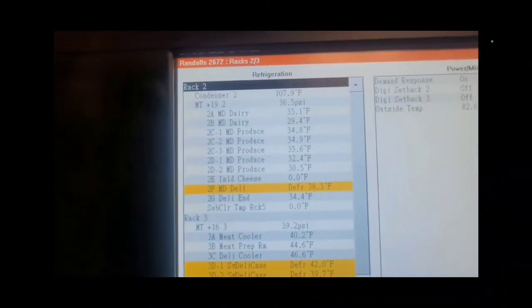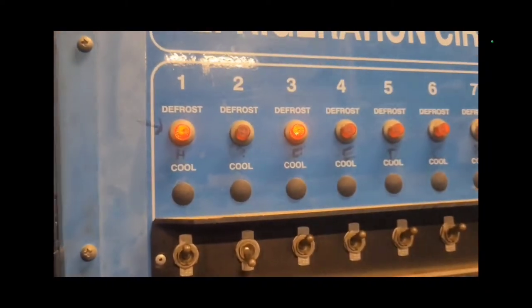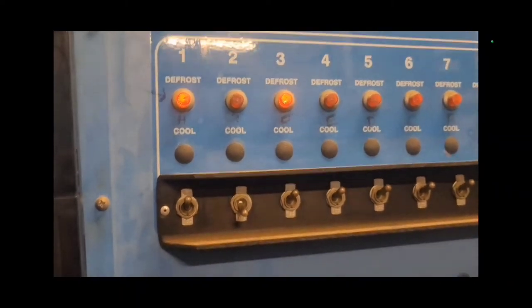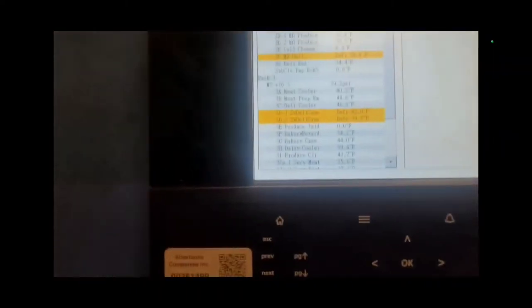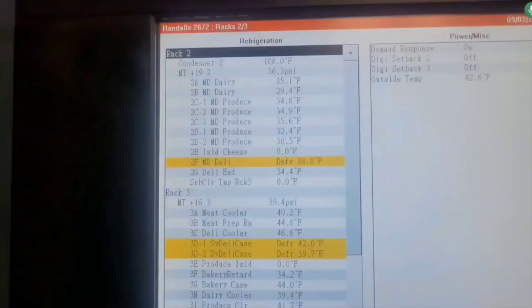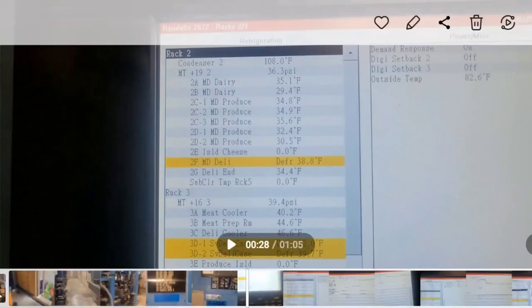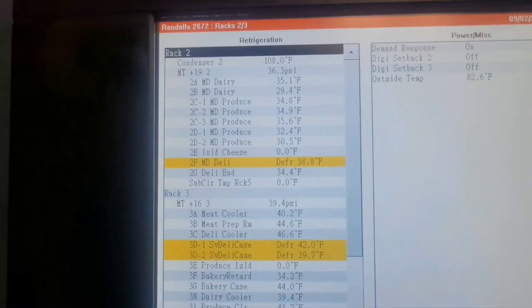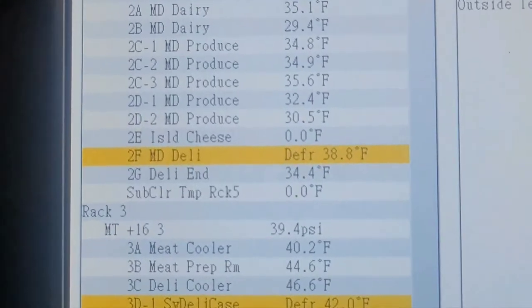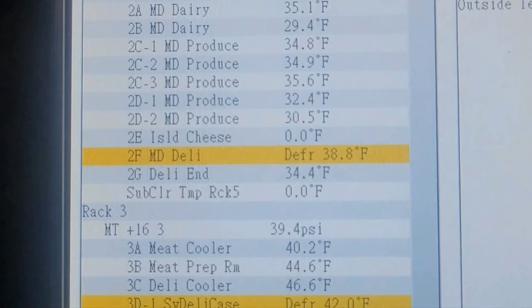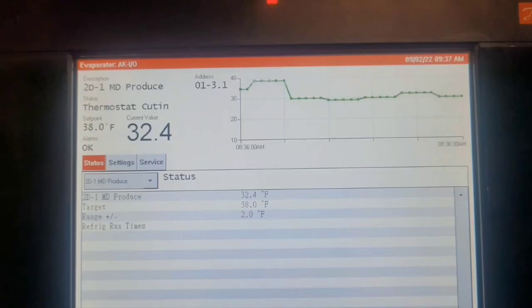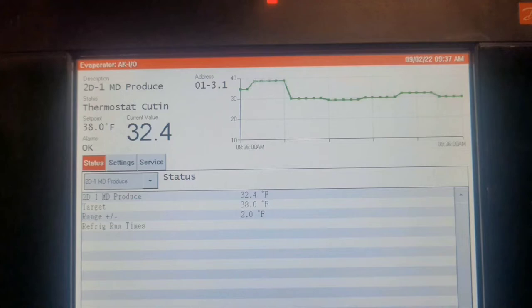Looking at the controller here, if you look closely, I've turned off 2D already. If you look at 2D, it's at 32.4, and the other one's 30.5. When I click on 2D1, you can see up here the set point is 38, but it's running at 32. It was actually colder a few minutes before I turned it off, running at like 29.5.